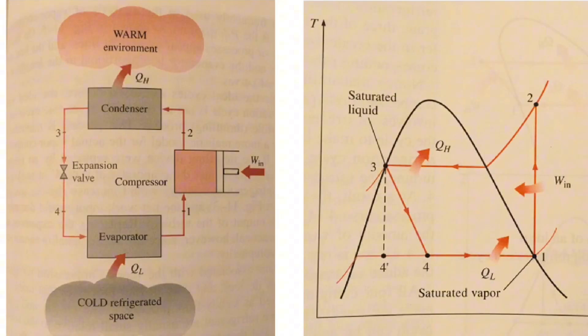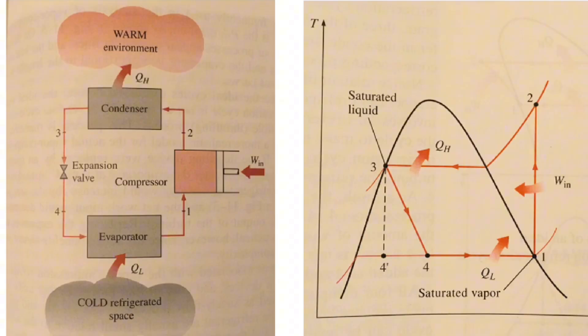In the diagram on the left side we can see the four components of the refrigeration cycle. At the evaporator, the cold refrigerated space drops its load, where heat is absorbed by the refrigerant passing through the piping. The heat from the load causes the refrigerant to evaporate. As it enters the compressor, work is added to compress the refrigerant, which then leaves at high pressure and goes into the condenser, where a fan expels the heat into the environment. The cooled refrigerant then enters the expansion valve, causing its temperature to drop.